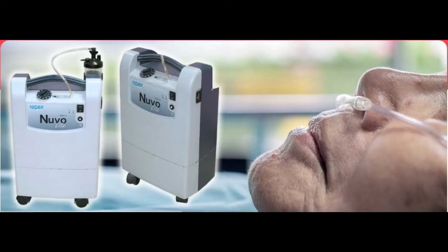Good morning, friends. Oxygen concentrators. Why are they in demand and how are they different from cylinders? An oxygen concentrator is a medical device that concentrates oxygen from ambient air. Atmospheric air has about 78% nitrogen and 21% oxygen, with other gases making up the remaining 1%.